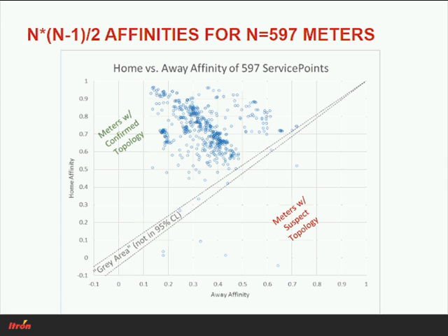Here are a few meters, and there are 6 of them, that clearly have been classified wrong. There's no way that a meter can correlate at 0.65 with another meter on another transformer and only at, in fact, slightly negative, which doesn't really mean much, to all the meters on its own transformer. This meter here, I would bet anybody an expensive dinner, is misassigned. And the same for these meters here.